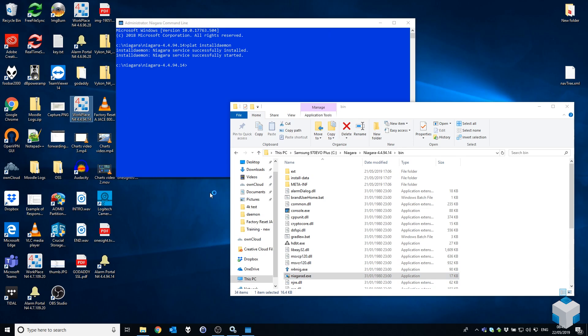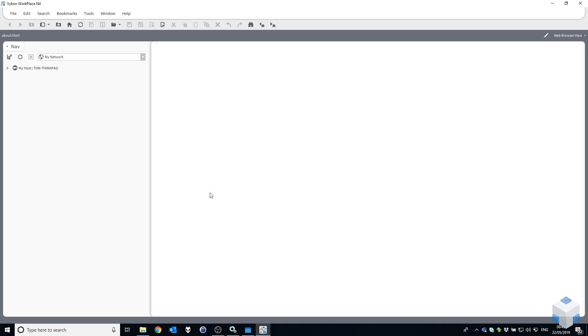There's no accidental crossover because you can actually open any version of workbench regardless of what platform daemon is running, but you may and likely will encounter strange problems that may or may not give you error messages. So it's always best practice: one version of workbench combined with the corresponding version of the platform daemon and you'll be good. That process you've just seen there can be repeated for any version of Niagara running on your machine.